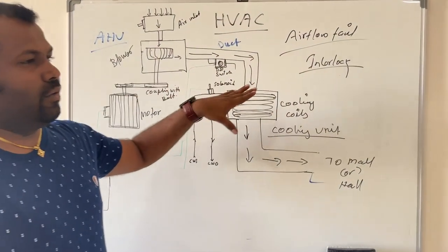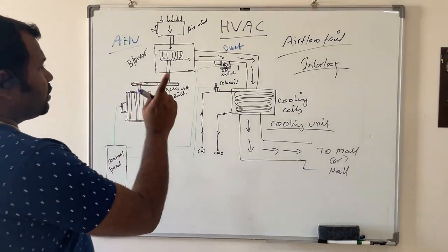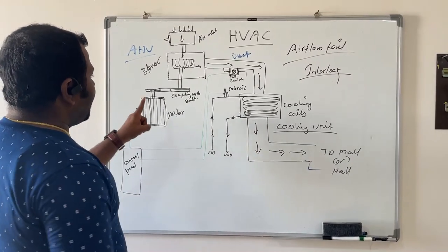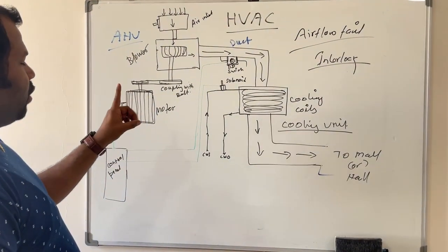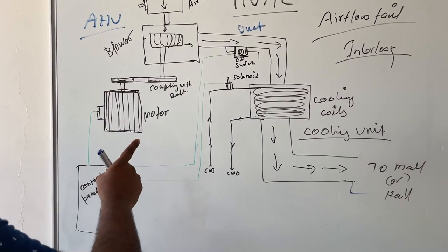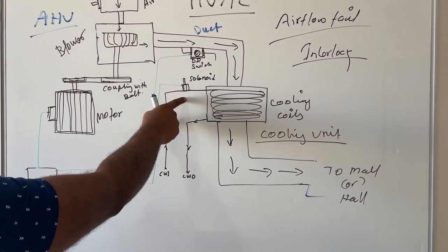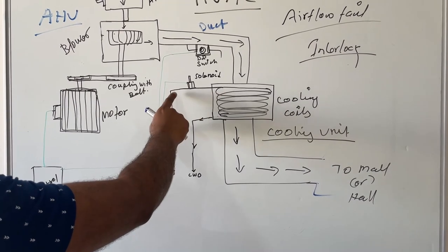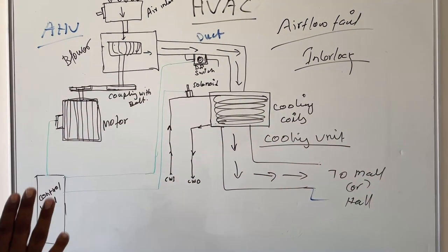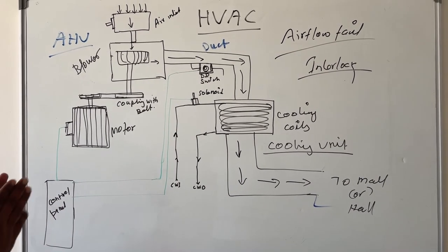To avoid this problem, we use the airflow fail interlock system. In the AHU system, the blower will be started first. Once this blower is started, then the supply will be given to the solenoid coil where cooling gas or cooling water will be circulated through the cooling coils.